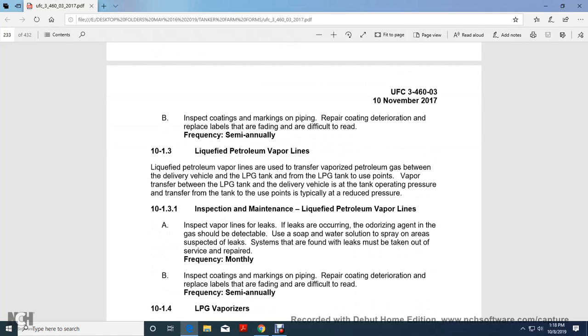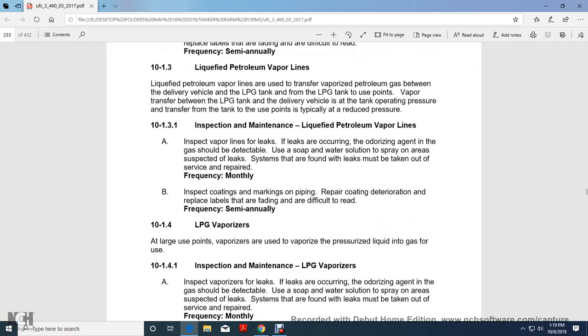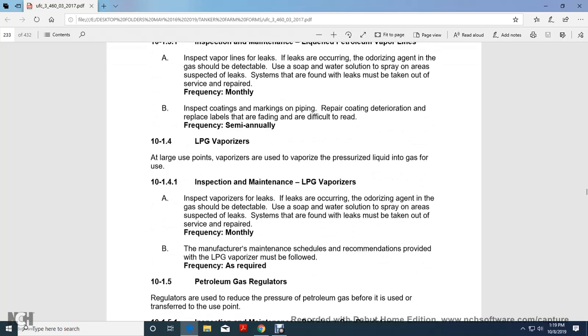Liquid Petroleum Vapor Lines. Liquid petroleum vapor lines are used to transfer vapor petroleum gas between the delivery vehicle and the liquid petroleum gas tank, and from the liquid petroleum gas tank to use points. Vapor transfer operates between the liquid petroleum gas tank and the delivery vehicle, at the tank operating pressure. Inspect vapor lines for leaks—the odorizing agent in the gas should be detectable. Use soap and water spray on suspected leak areas. Leaks must be taken out of service and repaired. Inspect coatings and markings of the piping and replace labels that are fading or difficult to read. Frequency: semi-annually.